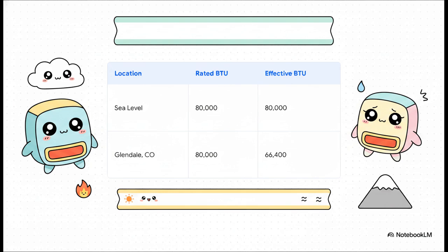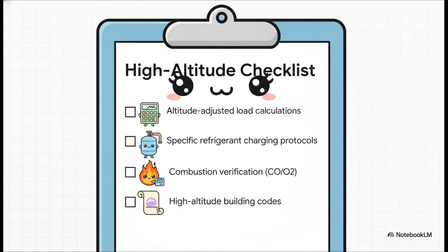If an installer ignores that simple fact, they are setting that system up for failure from the moment they turn it on. So surviving at altitude means you've got to check every one of these boxes: using those adjusted calculations, following different rules for charging refrigerant, understanding that combustion itself works differently with less oxygen, and following all the strict local codes designed for these conditions.